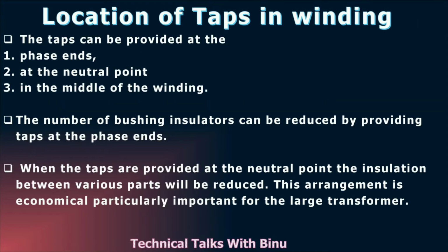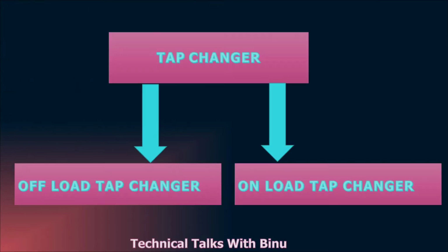Now we will see the position of taps in a winding. Taps are provided at phase ends, in the middle of the winding and at the neutral point. If you are providing the taps at the phase ends, then you will be able to reduce the number of bushings used. And if you are providing the taps at the neutral points, then you can reduce the requirement of insulation. Tap changers are basically classified into two. They are on-load tap changers and off-load tap changers. Now we will see in detail.